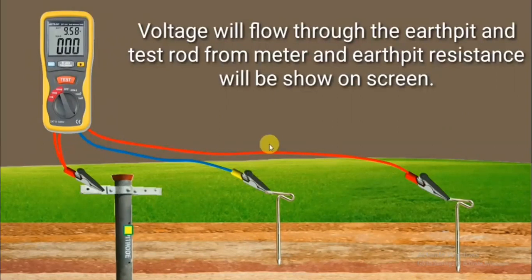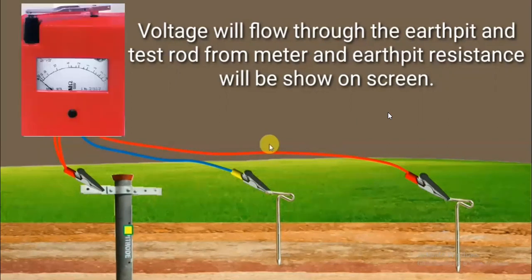That potential will flow to the earth pit, then ground, then through the electrode or test rod, then to the meter. So this meter will show the direct value of the earthing resistance or earth pit resistance. So it will give the final value of the resistance, which is measured with the help of this digital earth resistance meter. Suppose we have to use the Megger in order to measure the earth resistance. Simply replace the digital earth tester with this Megger. Then the Megger handle will rotate at a constant speed. If you rotate this Megger handle at a constant speed, it will give the value of the resistance, that is the earth resistance for this earth pit.